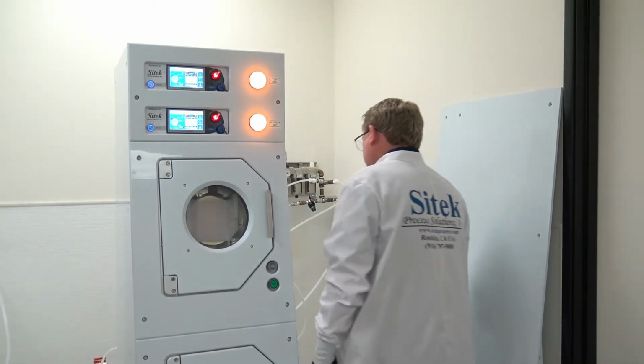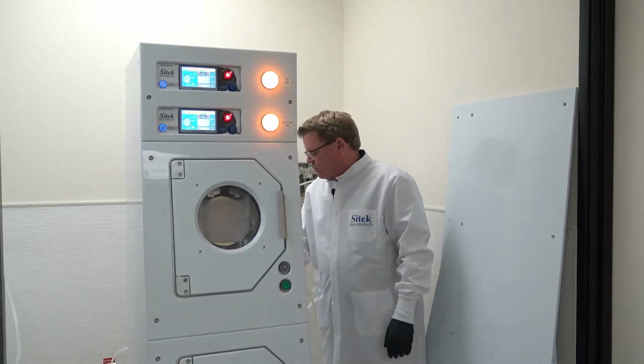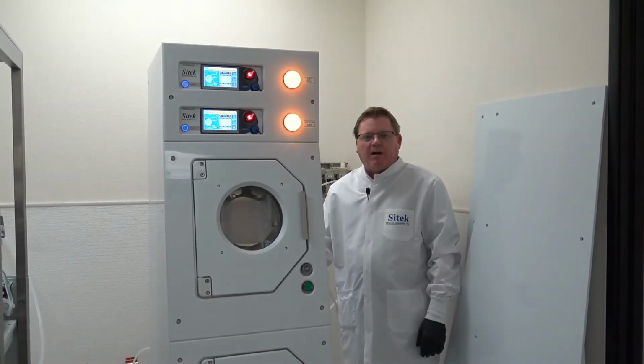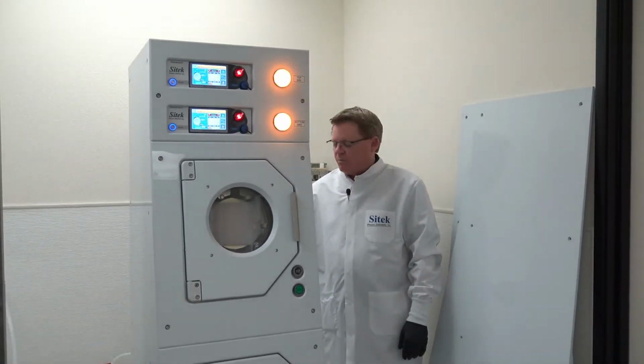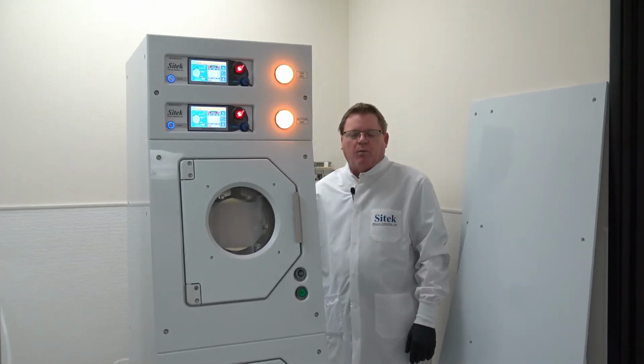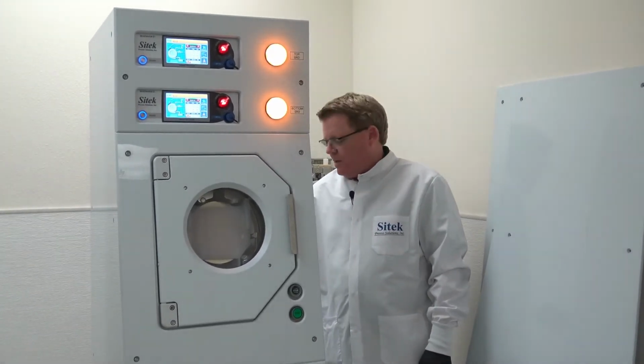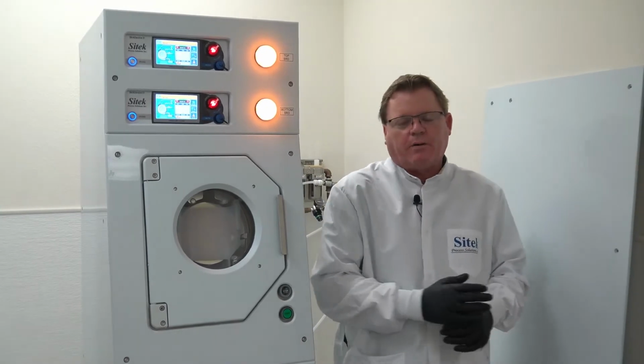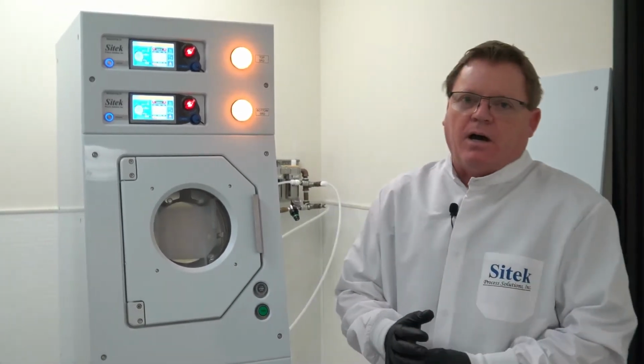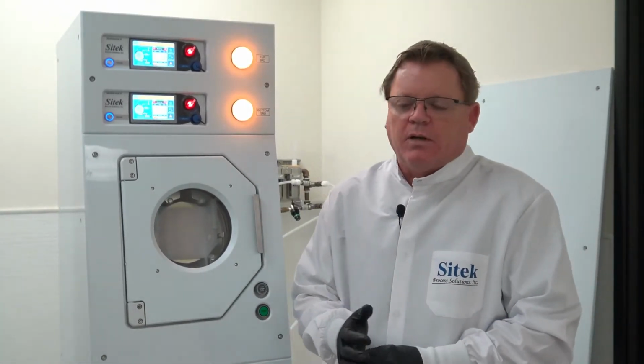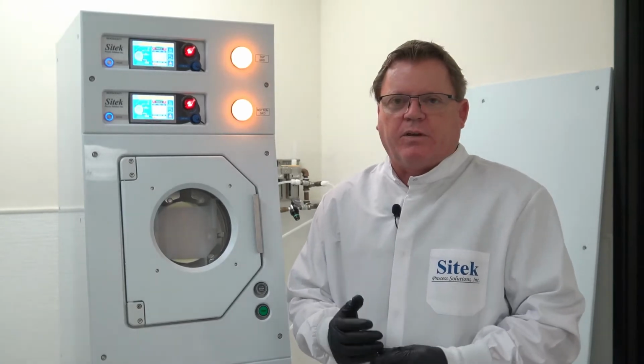I'll go to the back and I can see the water recirc valve here. It's a gray valve that allows adjustability for the customer. They can have it as full flow if they want the water recirc, or just a trickle. As many people in fabs know, the water recirc allows a non-dead leg status of the tool. When you have a dead leg, there's lots of history that will cause bacteria growth.